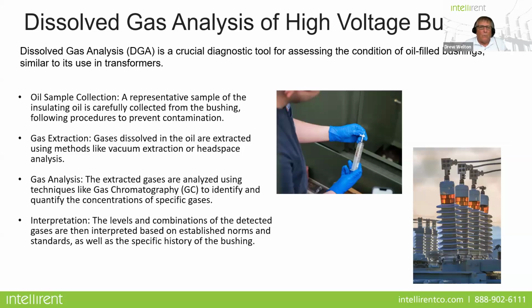Okay, now another thing that I want to touch on, and we'll finish up very soon so we can get to some questions, is your dissolved gas analysis on your high voltage bushings. Of course, we do this in transformers, and it's very important. Basically, an oil sample is collected, a representative sample of the insulating oil, carefully collected from the bushing following procedures to prevent contamination. Gases dissolved in the oil are extracted using methods like vacuum extraction or headspace analysis. The gases are then analyzed using chromatography to identify them, just like your transformer.